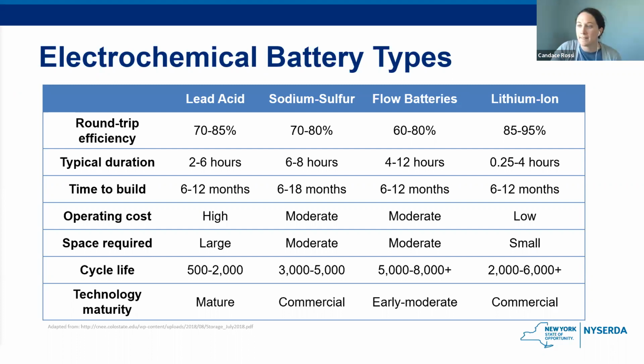So while we're looking at this chart, you can see that the lithium ion batteries tend to have a higher round trip efficiency than the other types. So less energy is being lost in the energy storage process. So, you're getting most of the energy you put into the battery back out of it as well. The typical duration is pretty standard, anywhere from 15 minutes to 4 hours, as well as the time to build, which is pretty standard across battery types.